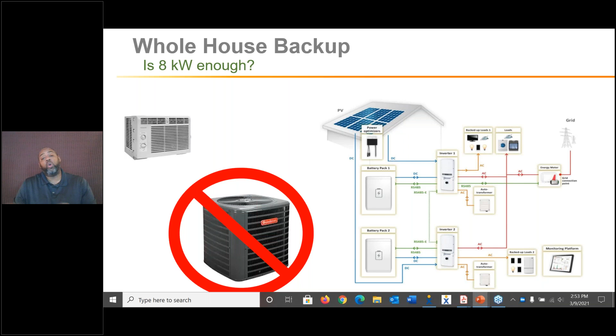Again, just showing you what could be on an 8 kW inverter. That sizing chart I showed before illustrates what can be on it — a main bedroom, home entryway, kitchen, refrigerator, internet. If you really wanted a hot water heater or air conditioning, you probably would want to add 2 inverters. Not saying you couldn't load-manage that, but on simple mathematical principle, if you wanted to add an air conditioner, most air conditioners are around 40 amps, so you'd need more flow, or more inverters.